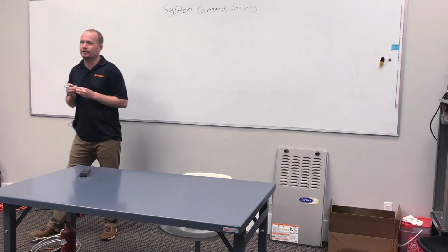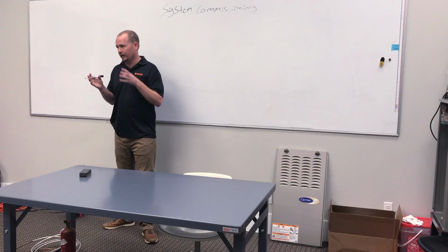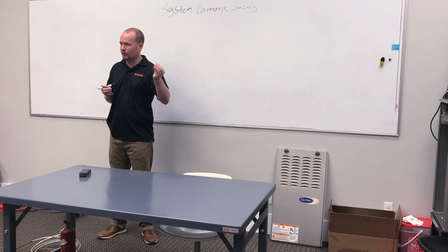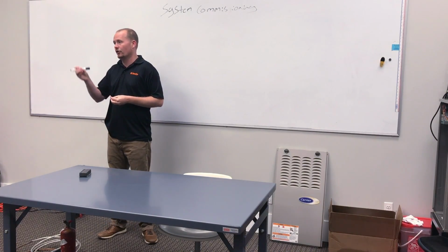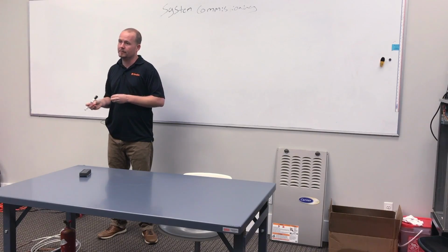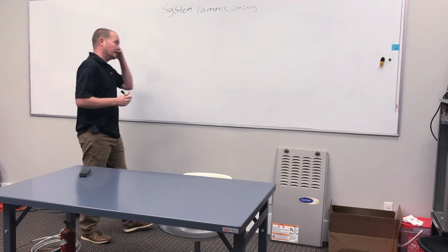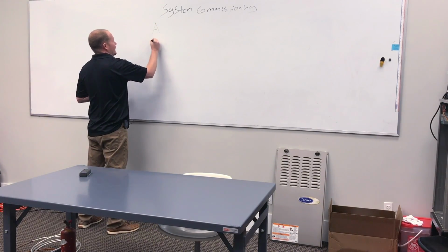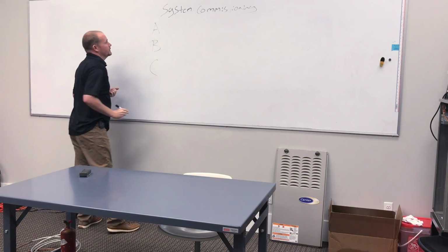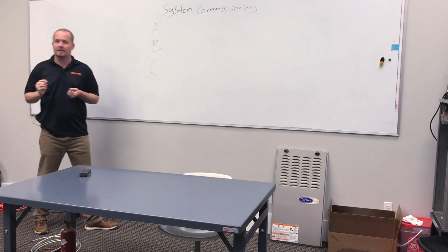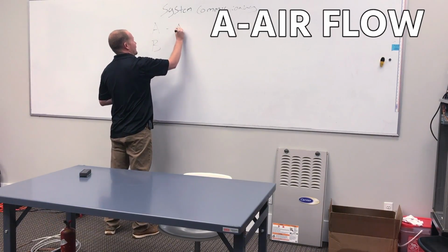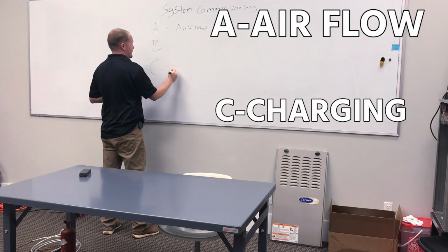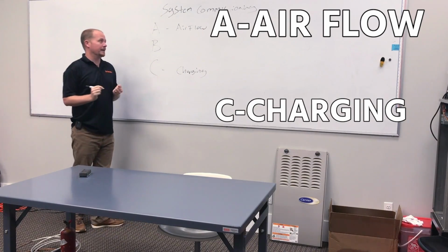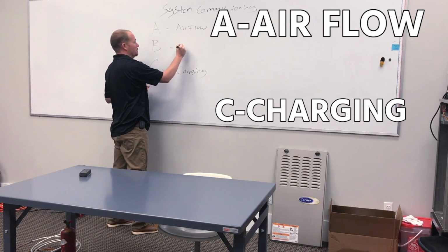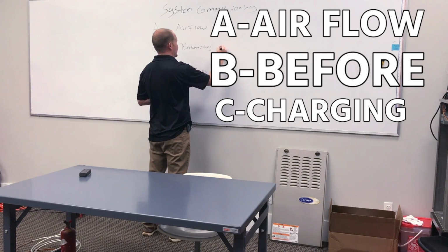Mostly it's any time that you interact with the airflow of the system or you interact with the charge of the system. So the refrigerant in the system or the airflow in the system. So we're going to talk about the ABCs. There are two different ways that people will talk about the ABCs. A is always airflow, C is always charging, but some people will say airflow balancing and some will say airflow before.